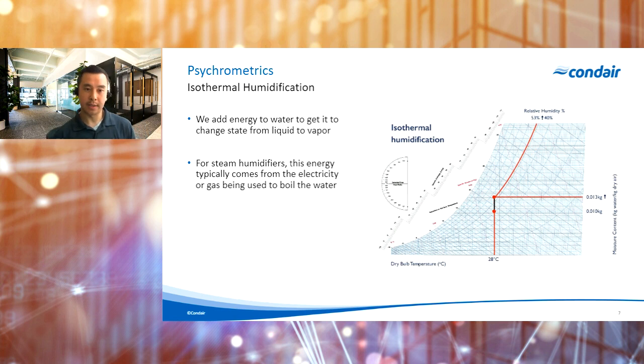Now, if we look at, in comparison, the isothermal process, as I mentioned, in this case, we're simply adding energy to the system to drive that phase change from liquid water to vapor. So that energy source is typically electricity or gas, either natural gas or propane, and we're effectively boiling that water to generate steam, which is then absorbed into the air, thus increasing that humidity. So we consider this effectively a constant temperature process. In reality, depending on the method of steam distribution, which is typically a steam grid in the airstream, distributing steam into that air supply, there may be in reality a 1 to 2 degree temperature increase, but for any of the calculations that we're doing, any of the processes that we're looking at, we're effectively assuming this is a constant temperature process.